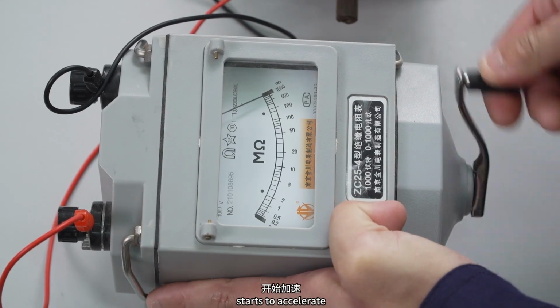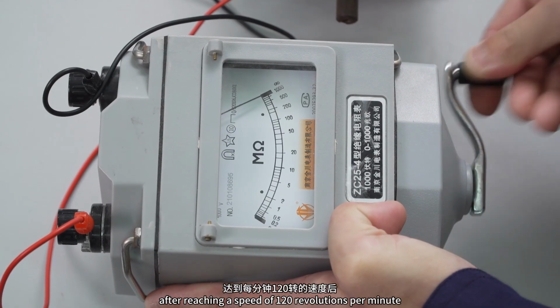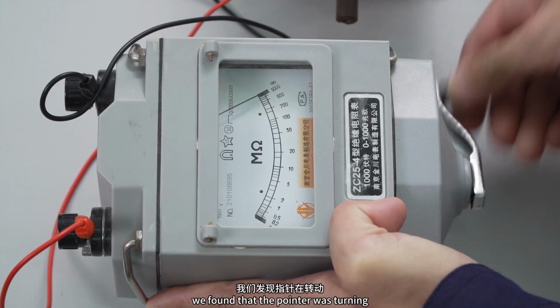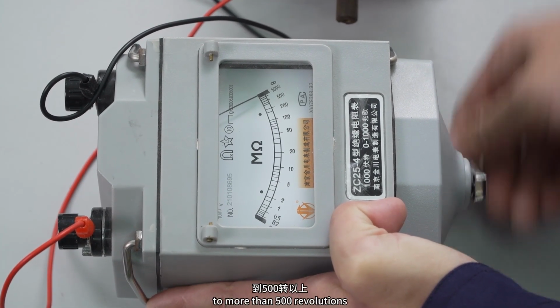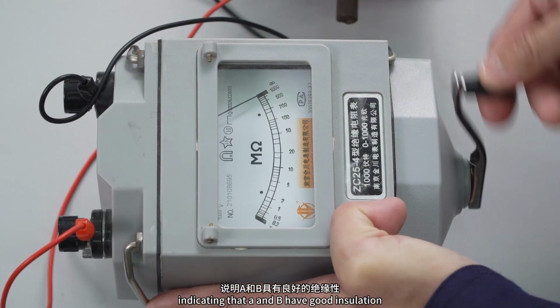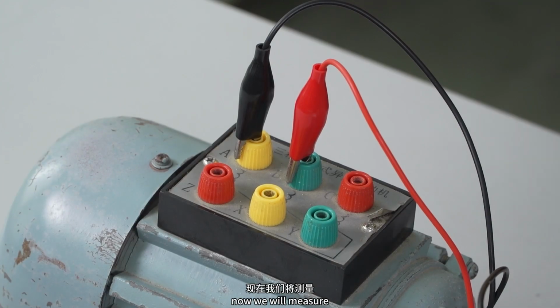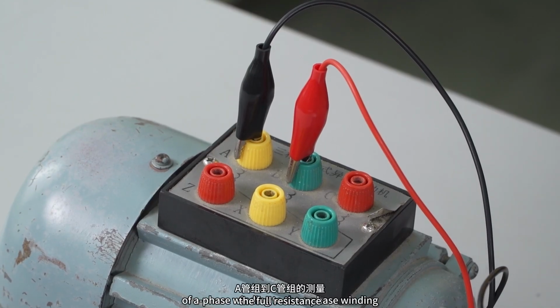Starts to accelerate. After reaching a speed of 120 revolutions per minute, we found that the pointer was turning to more than 500, indicating that A and B have good insulation. Slowly stop. Now we will measure the insulation resistance of the A phase winding to the C phase winding.